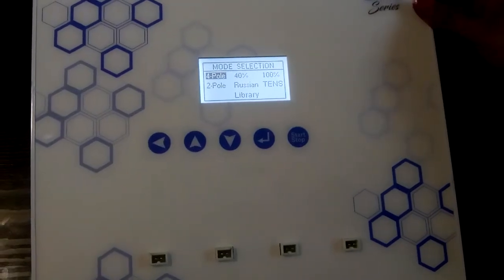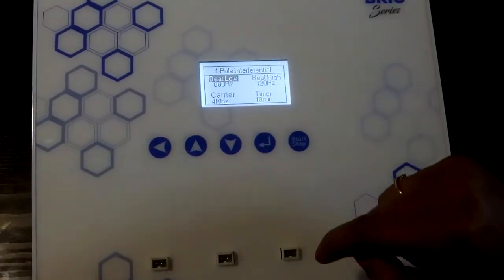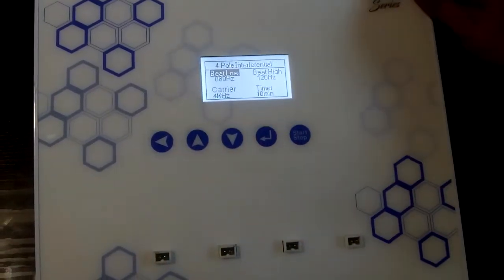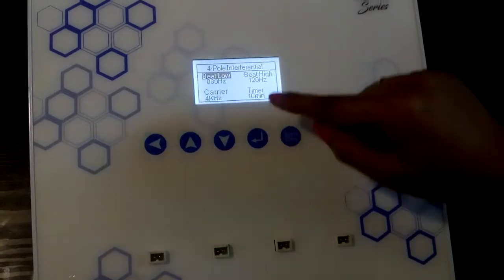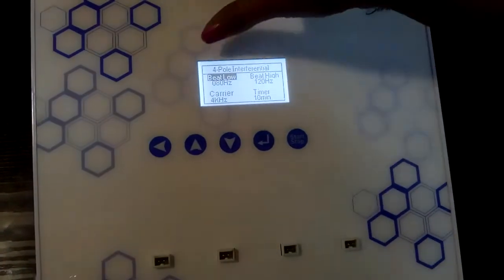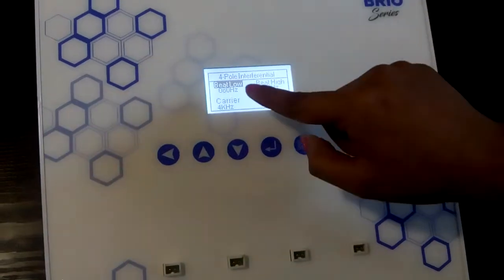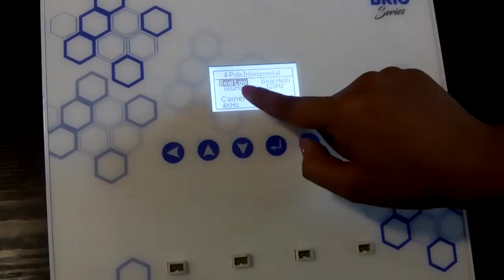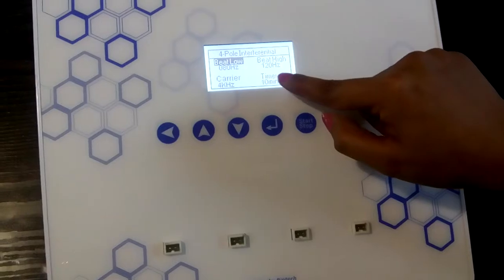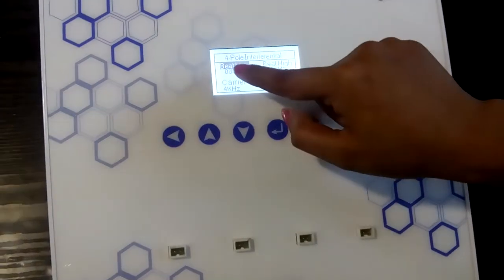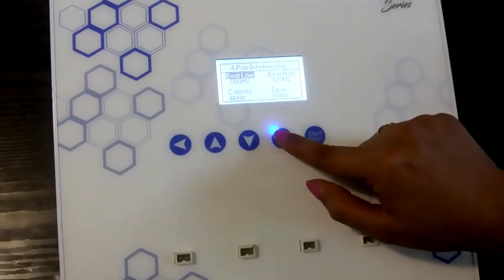Now let us set the 4-pole parameters. To set the 4-pole parameters, press the enter button. Once we are in the 4-pole interferential setup screen, you can see the options of beat low, beat high, carrier frequency, and timer. To change the beat low frequency, press the enter button once.